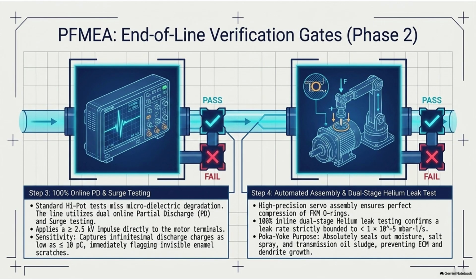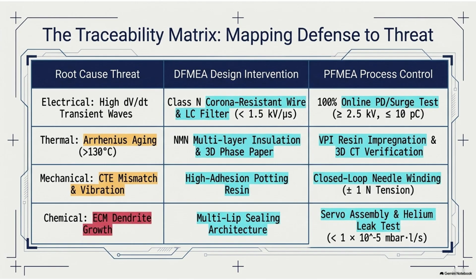Yeah. Why does it have to be that precise? Because of friction. If the machine pulls the wire even slightly too tight as it forces it into the steel slot, it will drag against the metal and scratch the armor. That drag will create microscopic scratches in the nanoparticle enamel. If you thin the armor by even a fraction of a millimeter, the electrical field will mathematically concentrate on that weak point, and the insulation will fail years prematurely. So they essentially have to handle this heavy copper wire with the delicacy of glass.